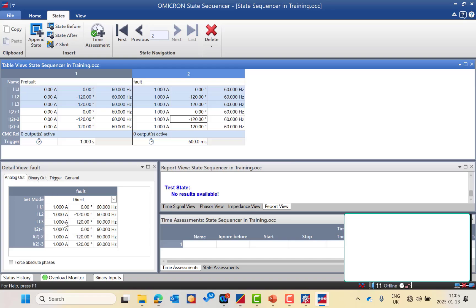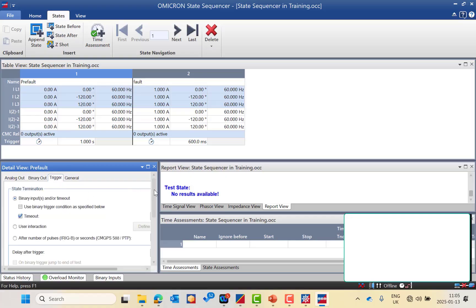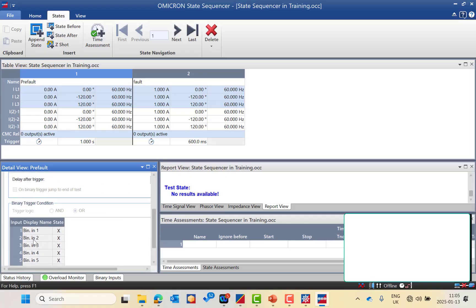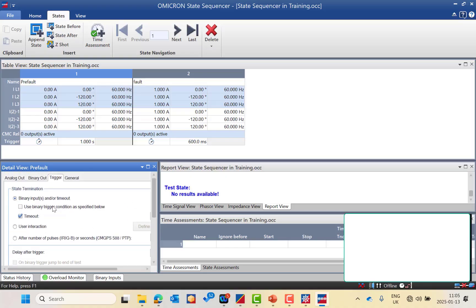As you can see, here is the analog output view for state 2, and here is for state 1 — which we named pre-fault and fault. Here is the binary output. If you need to simulate any kind of event, click the binary output to be active, and wire binary output 1 to the binary input of the protection relay. For any trigger on binary input 1 to switch off the injection, use the binary trigger condition as shown in blue.